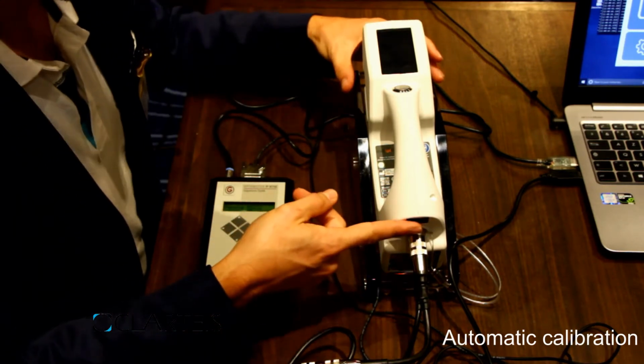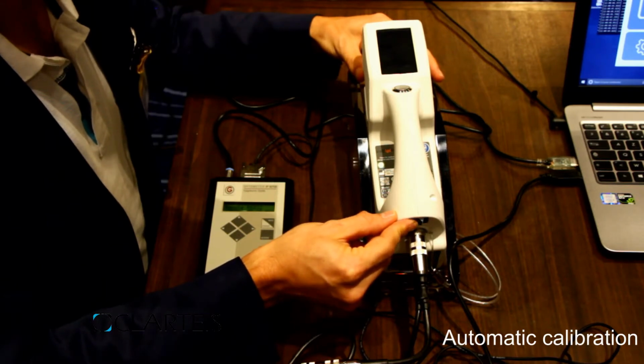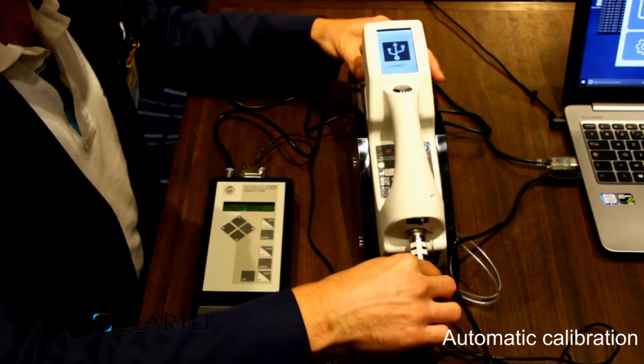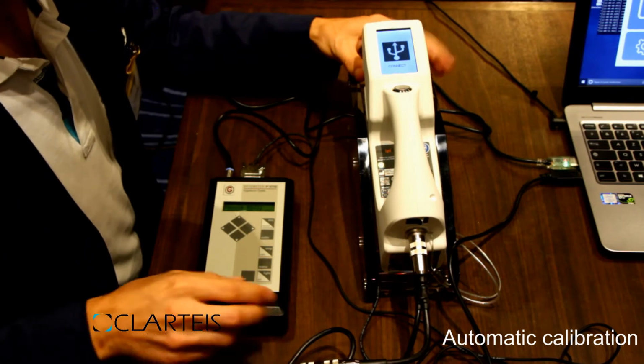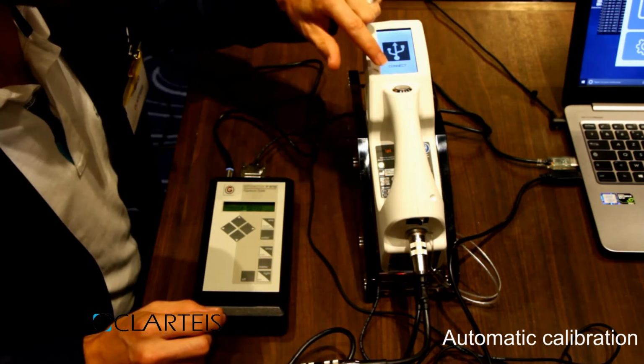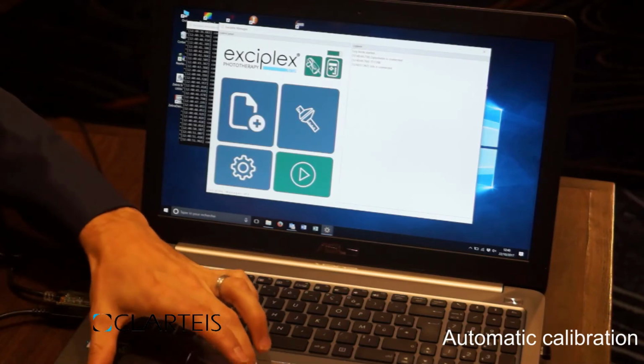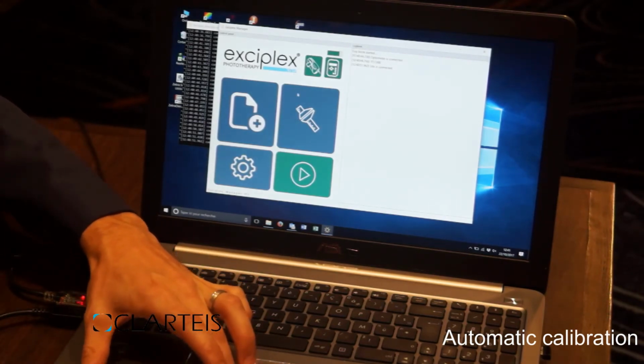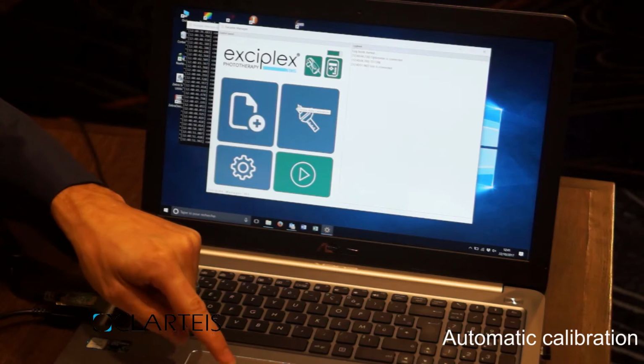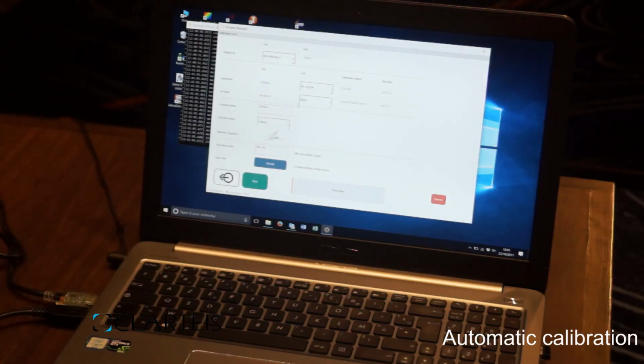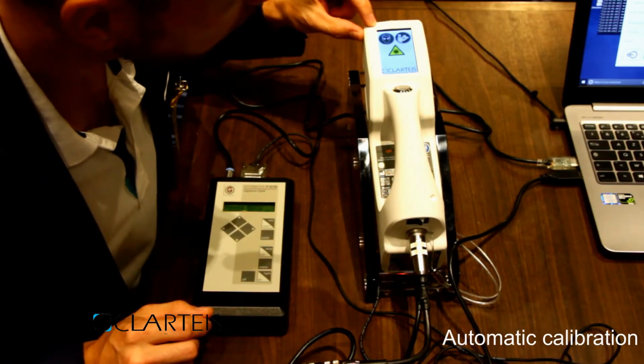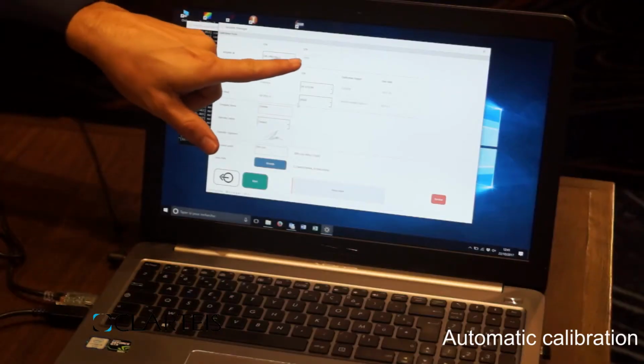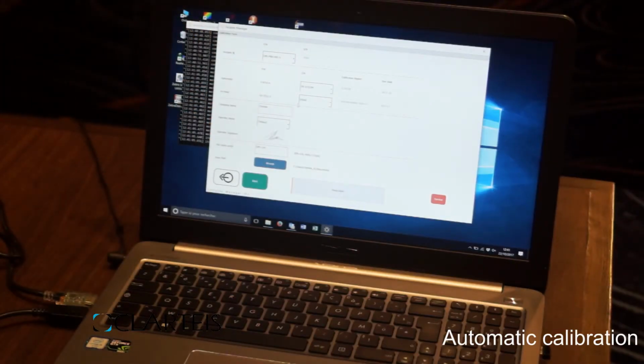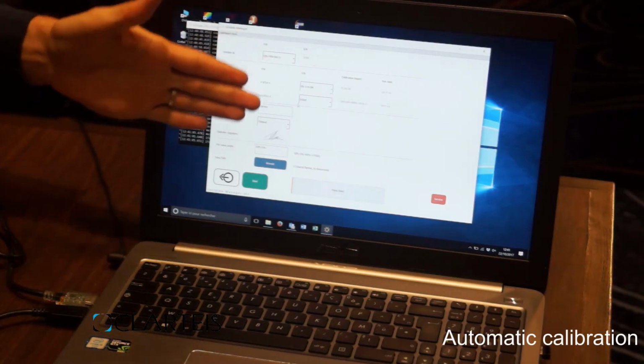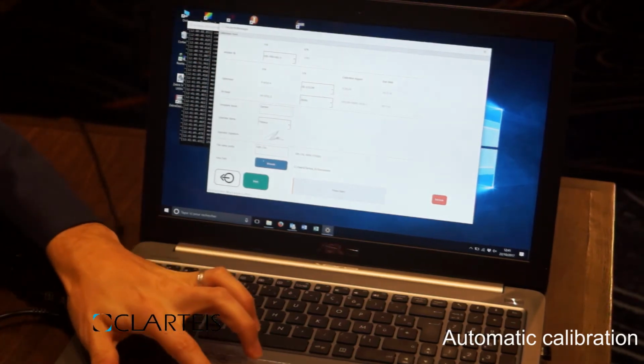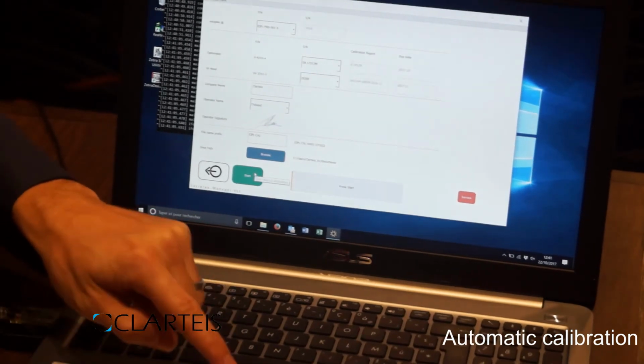Now you can turn on the Exciplex. As soon as the Exciplex is connected with the Y cable, it will be on the USB mode. Now you can go to the application and go to the calibration menu. The Exciplex starts itself, and it has been detected. Here you can see the serial number. You will have to fill all the form, and now you can start the calibration.